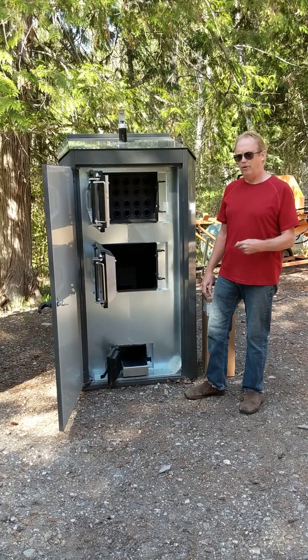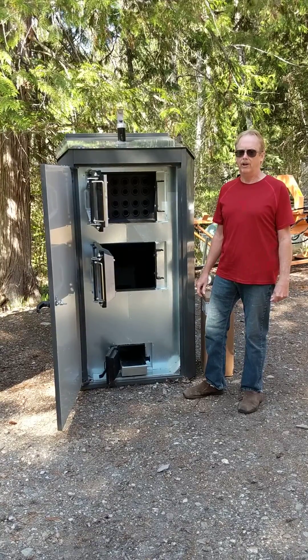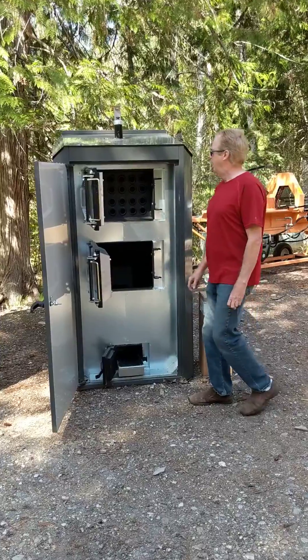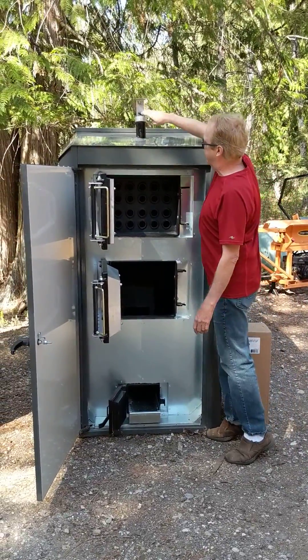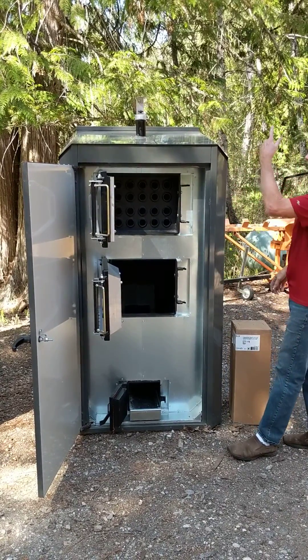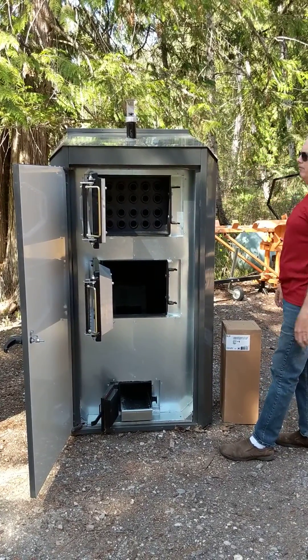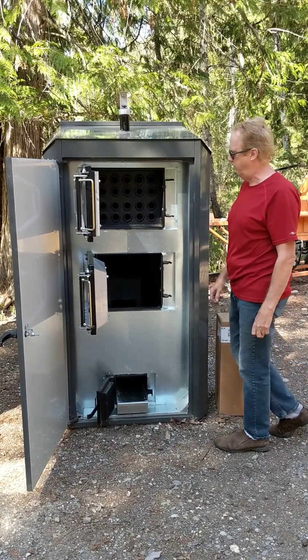We'll do a quick walk around here, and then I'm going to do another video showing you the one we actually have working in our place. It looks like the EGR 250, the log burning unit — same theory. This is where the water is added. The water glycol mix is easy to monitor; if it needs water you can add it. Typically they don't use too much water — maybe part of a gallon a month.